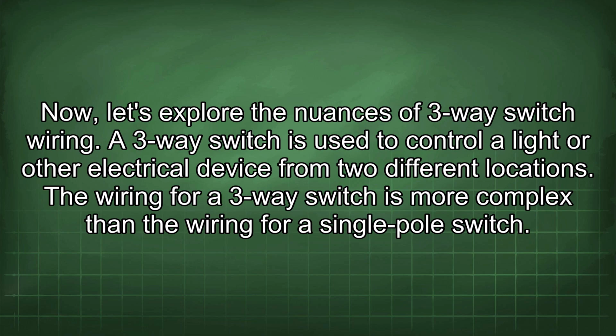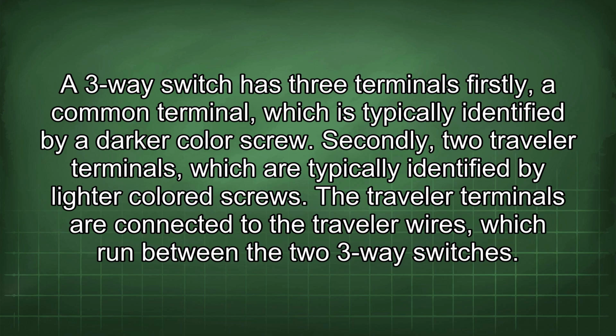A three-way switch is used to control a light or other electrical device from two different locations. The wiring for a three-way switch is more complex than the wiring for a single-pole switch. A three-way switch has three terminals. Firstly, a common terminal, which is typically identified by a darker color screw. Secondly, two traveler terminals, which are typically identified by lighter colored screws. The traveler terminals are connected to the traveler wires which run between the two three-way switches.